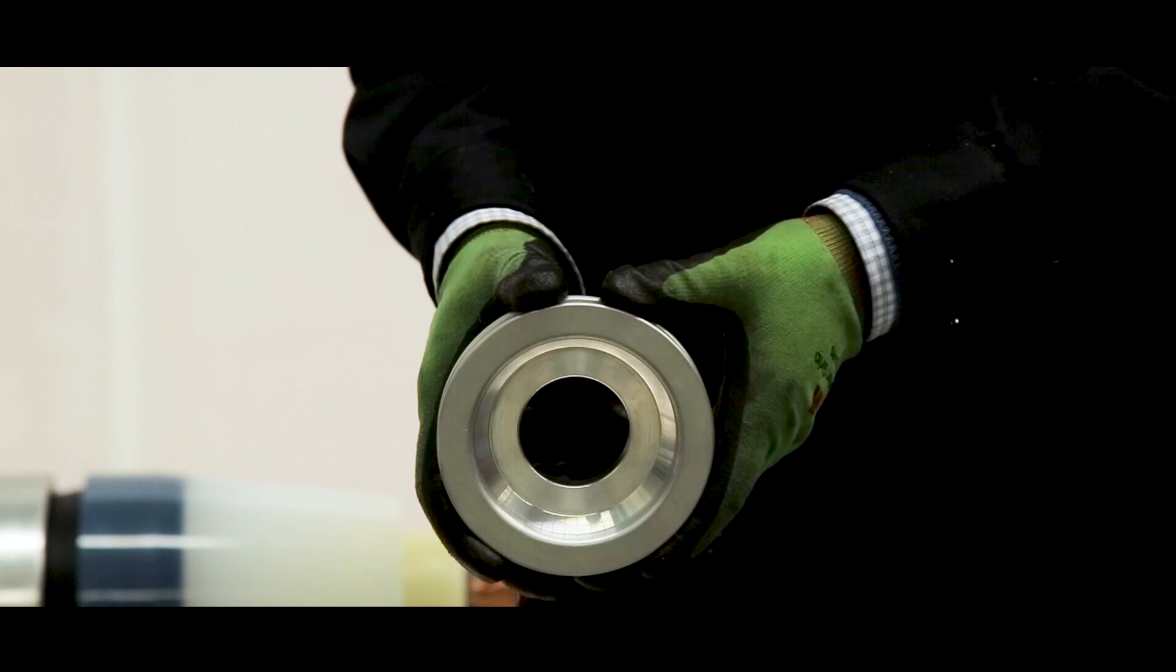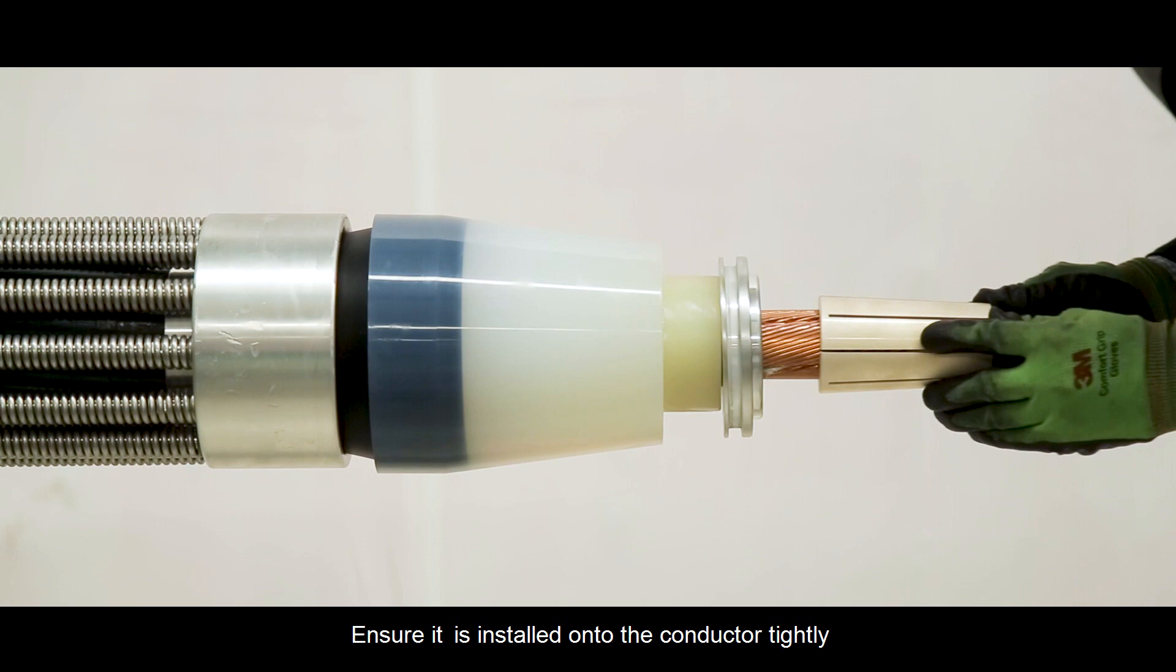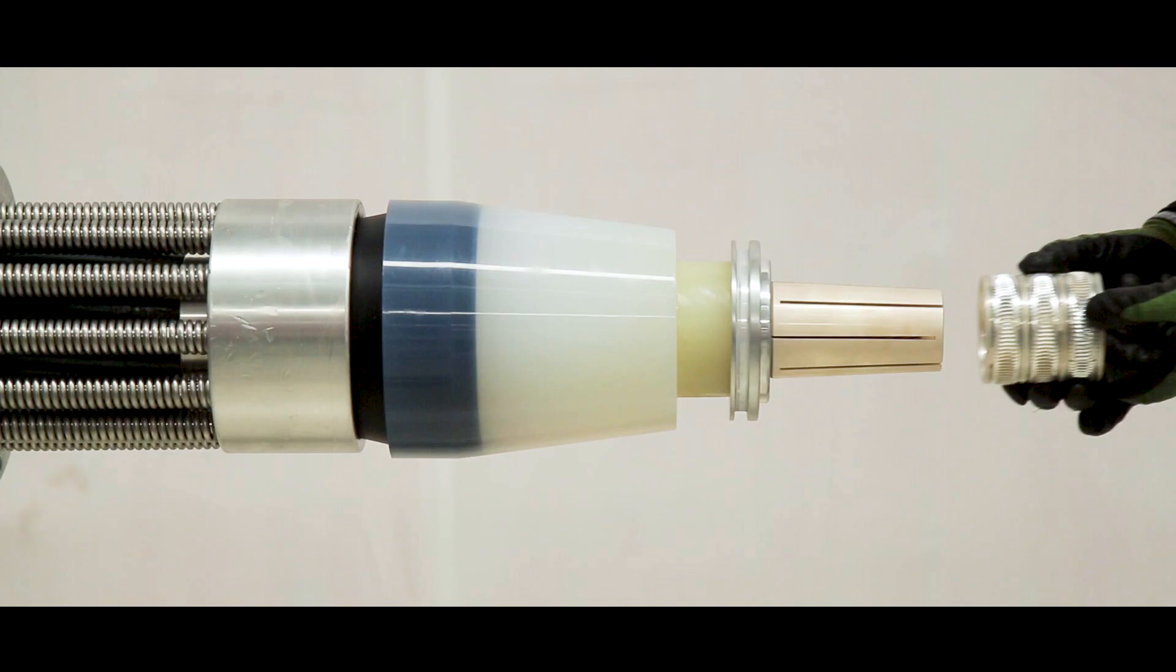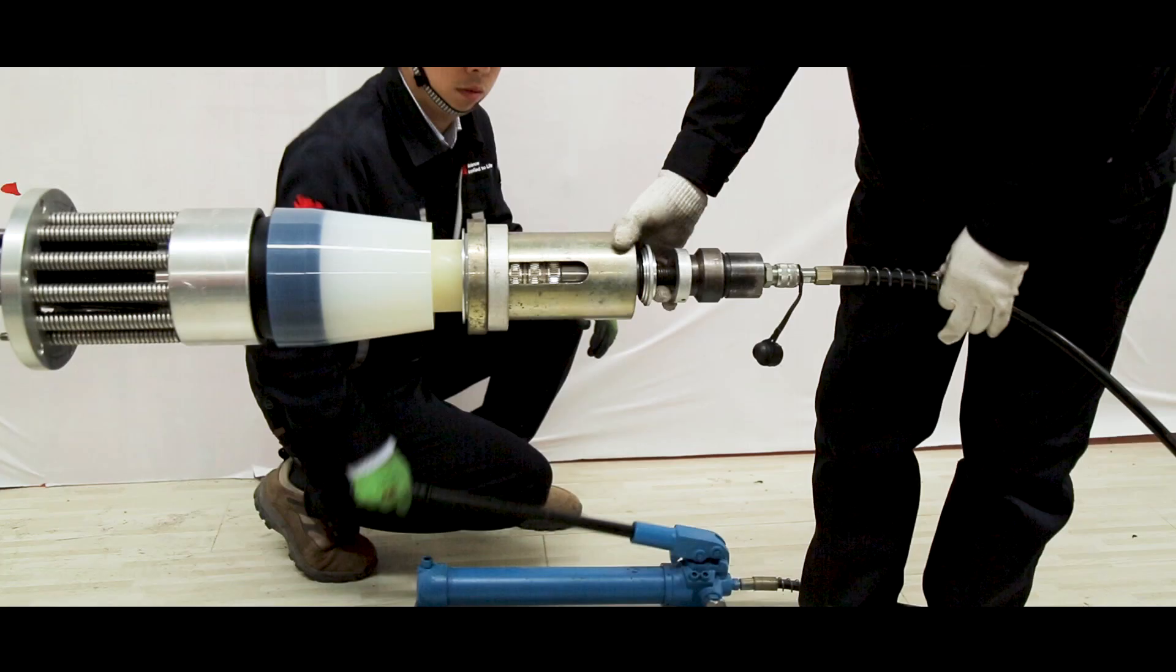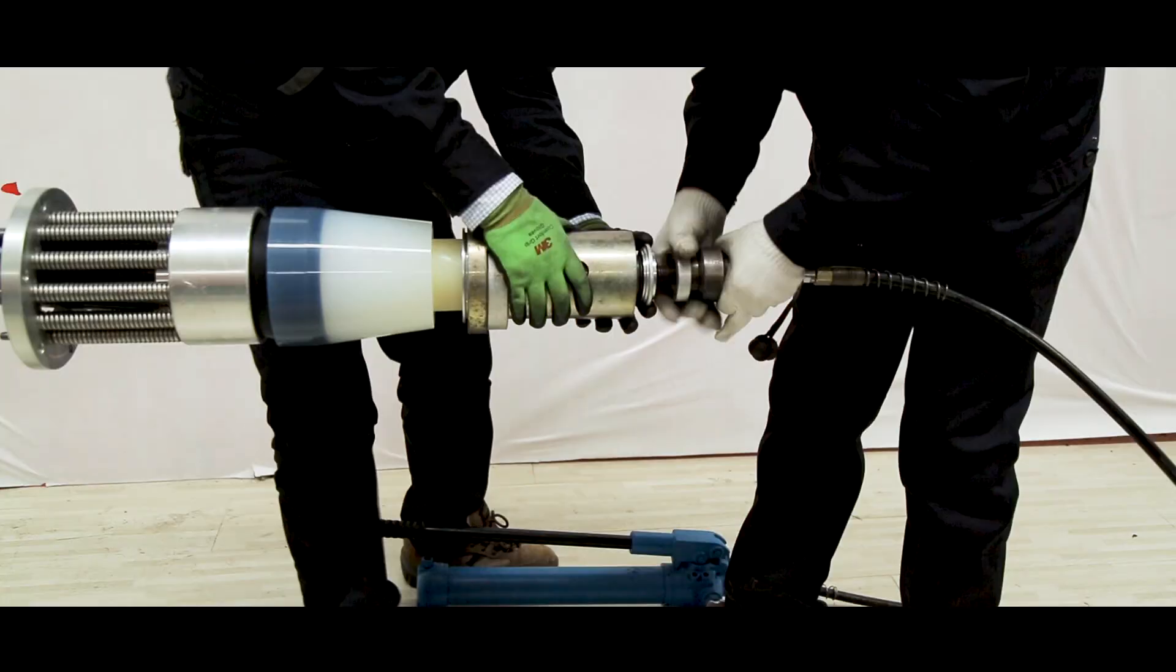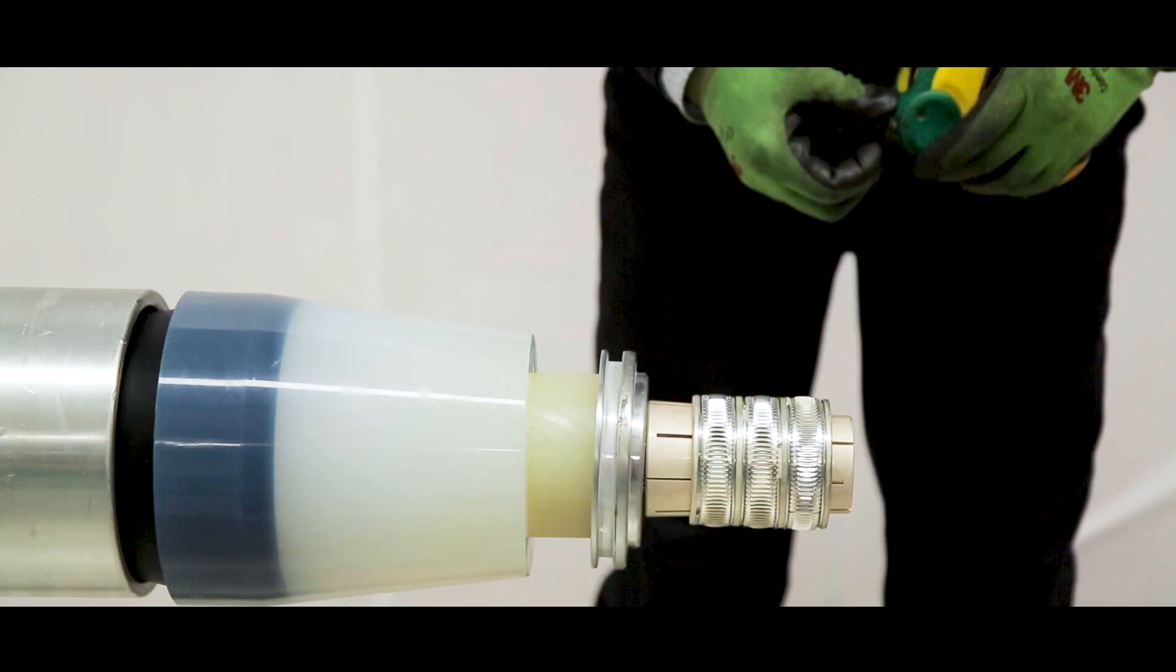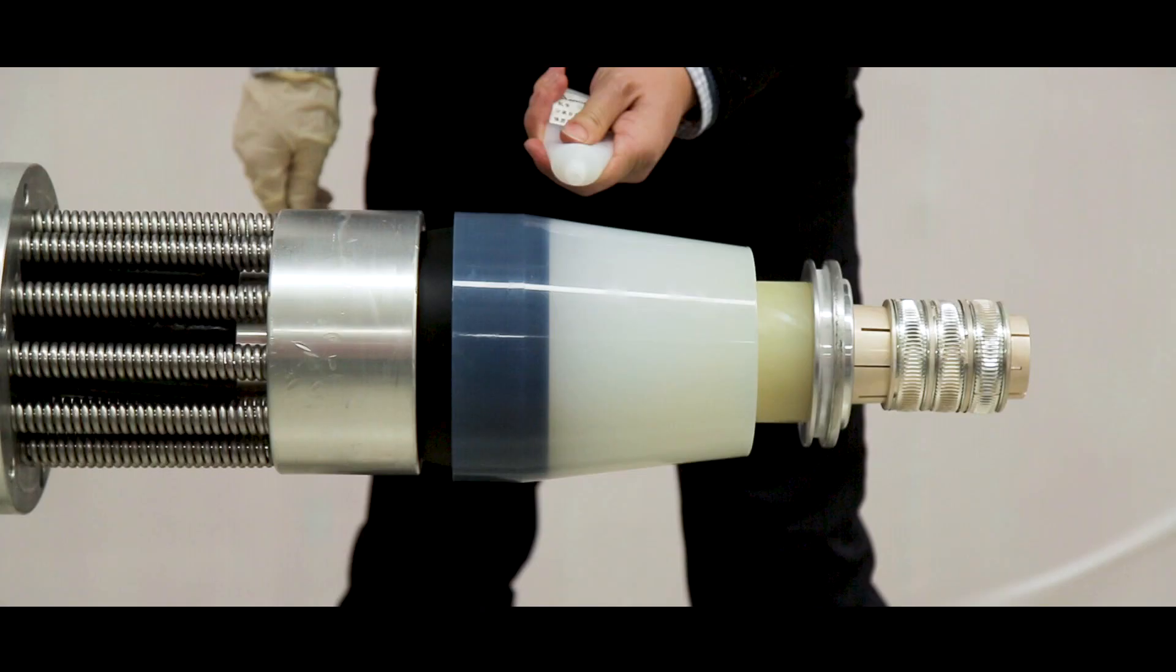Slide the metal pressure ring onto the cable. Install the plug-in assembly using special pushing tools. Ensure it is installed onto the conductor tightly. The distance to the top of the pressure ring should be equal or slightly more than 13 mm.